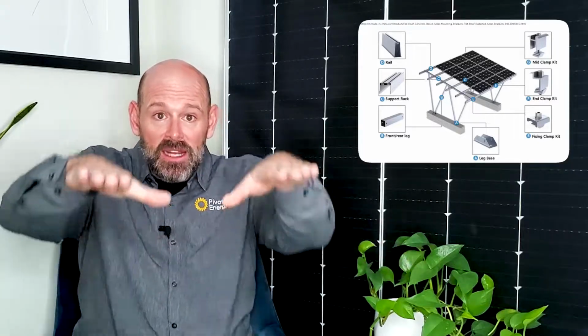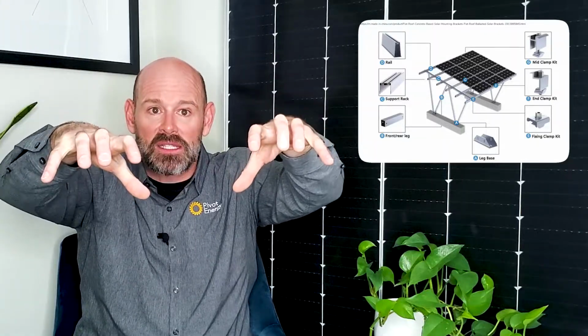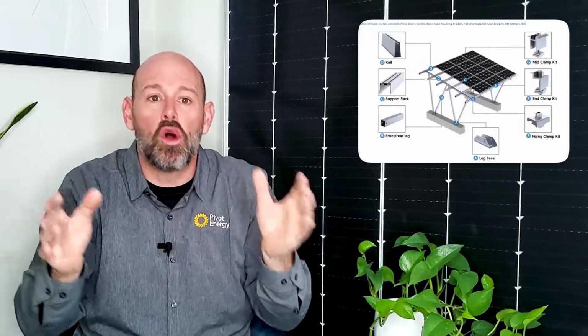It is very unlikely for a solar panel installation to damage your roof, which is why so many building owners are installing solar. As we mentioned earlier, one of the most common commercial installation types is a ballasted system, which is a typical installation on a flat roof. With a ballasted racking installation, the solar panels are mounted on a racking system that has ballast trays that sit on top of the roof surface and then are held down by ballast blocks, which are effectively heavy concrete blocks. For most roofs, this means no roof penetrations are required to install that system.